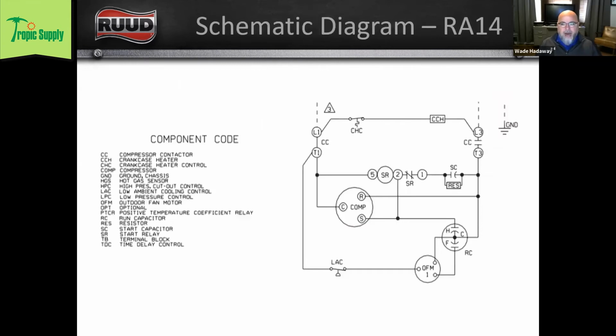So this is a schematic for the components in the outdoor section, obviously, of an RA14. These are our loads and our switches and our safeties. There's always a legend with a wiring diagram. Well, I shouldn't say always. There should always be a legend with a wiring diagram to let you know what's what. Some of these things are pretty obvious, right? That big circle in the middle, that's our compressor. Below that, we've got an outdoor fan motor, a run capacitor, etc. The dotted lines represent field wiring. That's where our line voltage from the disconnect wires into our terminal block.